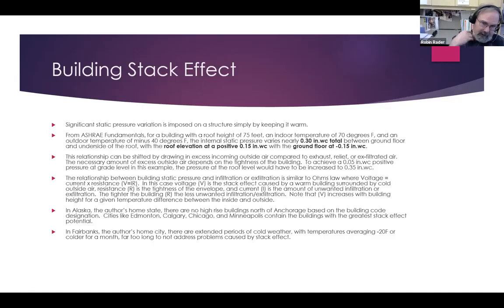So the relationship between static pressure and infiltration and exfiltration is similar to Ohm's law, where voltage equals current times resistance. In this case, the voltage is the same as the stack effect. The resistance is the tightness of the envelope, and the current is the amount of infiltration or exfiltration. So the tighter the building, the greater the R, the less unwanted infiltration and exfiltration.